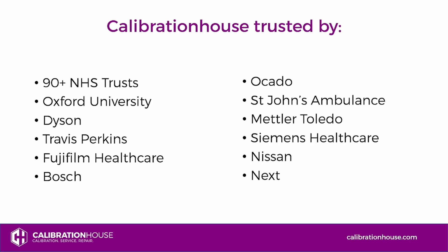So, what is calibration? Calibration answers the question, is my measuring device accurate? It's the process of checking a measuring instrument to determine if it is accurate compared to standards held at national or international metrology institutes. It's not an adjustment, as many people believe. The reason this misconception exists is because often the calibrating company will adjust the unit back to accuracy for free.